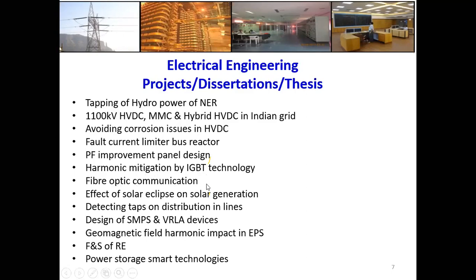Then fiber optic communication, which is also an emerging technology as PMUs take data from fiber optics communication. People are going for development of fiber optic communication. Our present PLCC communication used earth wires, which was old technology. Now we have already started replacing earth wires with OPGW, optical ground wires. You can work on this OPGW fiber optics communication technology, which opens the door for using transmission towers for communication, and it is the fastest communication at the speed of light, which will be better for us.